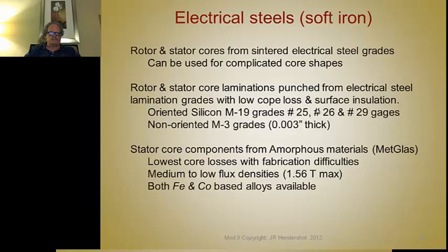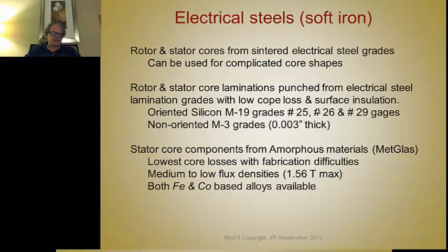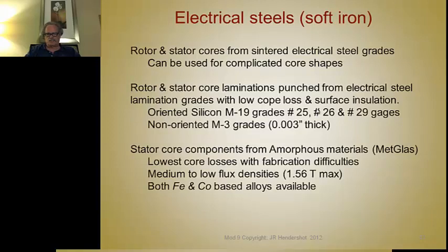The punched iron materials are made from electrical steels that have been rolled out to thin, accurate gauge thicknesses. The most common ones are 24 gauge, 26 gauge, and 29 gauge. The 24 gauge is 25 thousandths of an inch thick, 26 gauge is 18.5 thousandths thick, and 29 gauge is 14 thousandths thick.